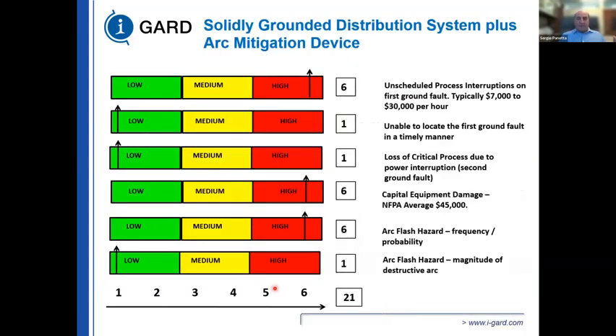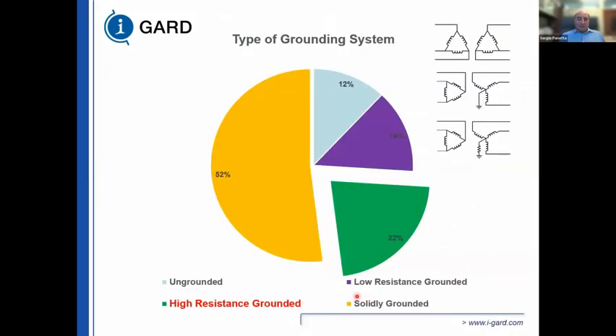So again, for the solidly grounded system with an arc flash detection relay, we've lowered the arc flash magnitude from 26 to 21 because of the presence of the arc flash relay. So we've put in equipment that will save personnel. So we're going to discuss high resistance grounding now.